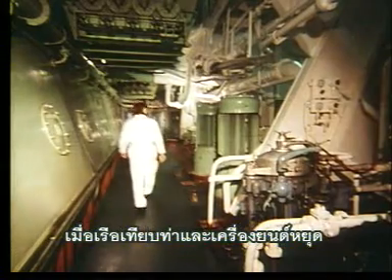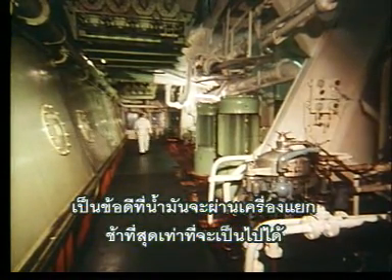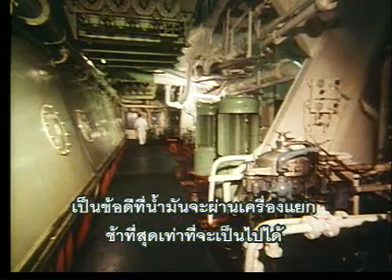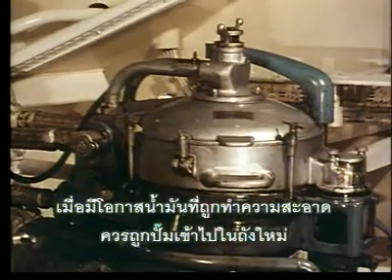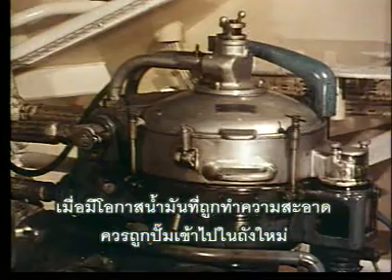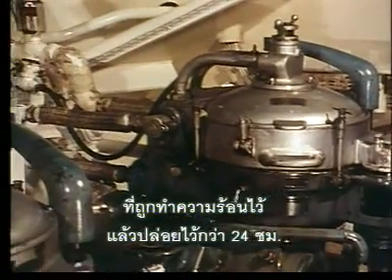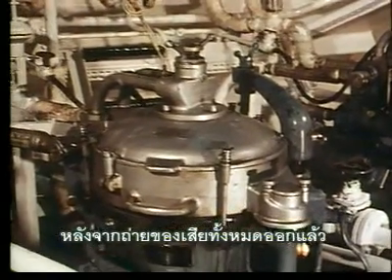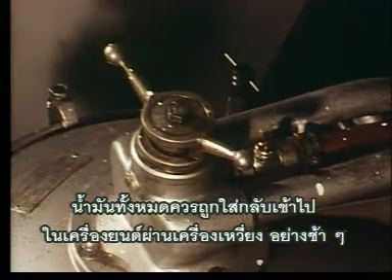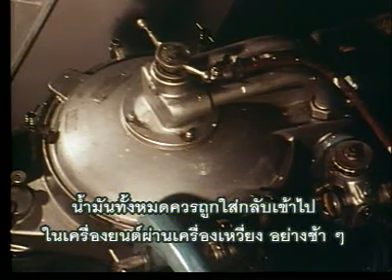When in port and the engine stopped, it is advantageous that the oil be passed through the separator at the slowest possible speed to take out smaller particles of contamination. When opportunity allows, the complete oil charge should be pumped to a renovating tank, where it is heated and settled over 24 hours. After draining off the impurities, all the oil should be run back to the engine via the centrifuge as slowly as possible.